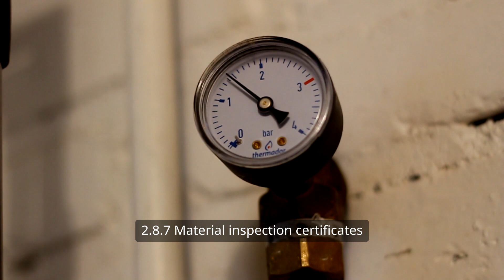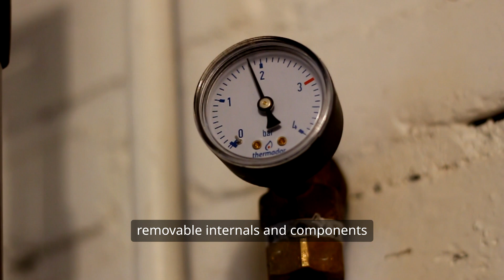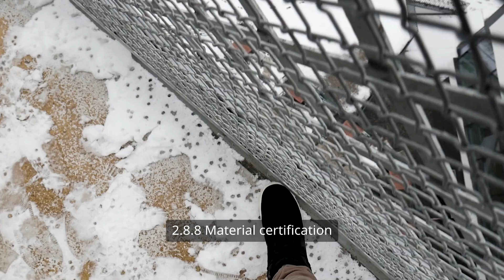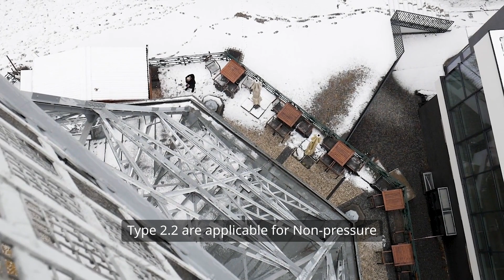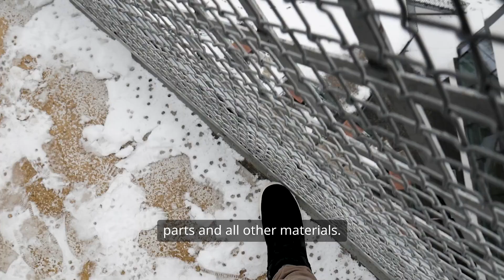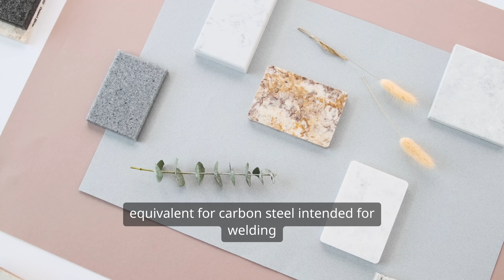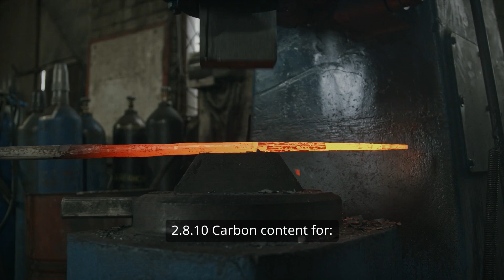2.8.7 Material Inspection Certificates. Type 3.1 also are applicable for removable internals and components welded to pressure-containing parts. 2.8.8 Material Certification Type 2.2 are applicable for non-pressure parts and all other materials. 2.8.9 Carbon equivalent for carbon steel intended for welding shall not exceed 0.43% based on the formula.